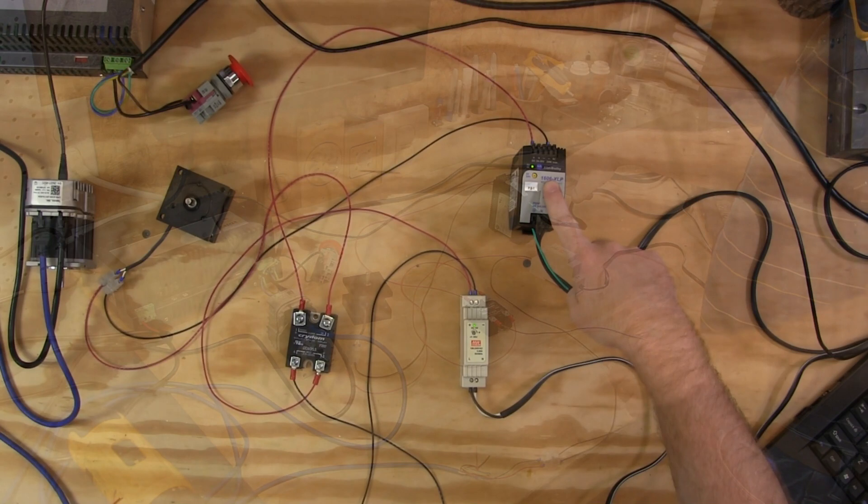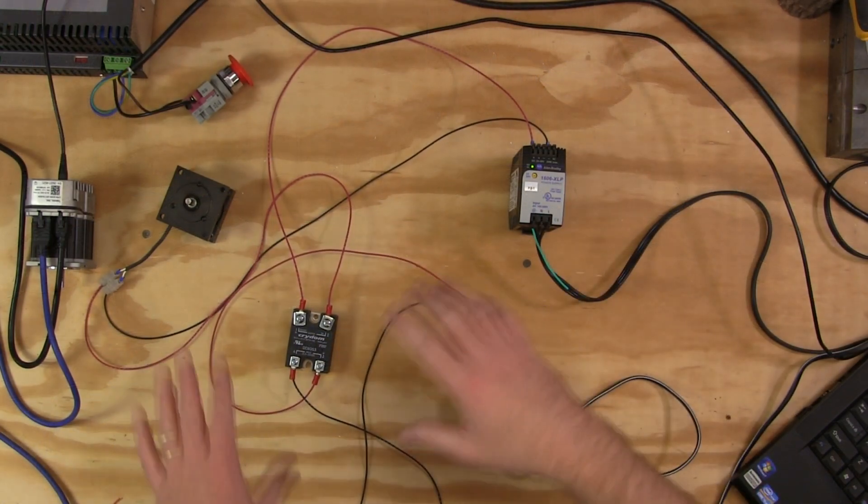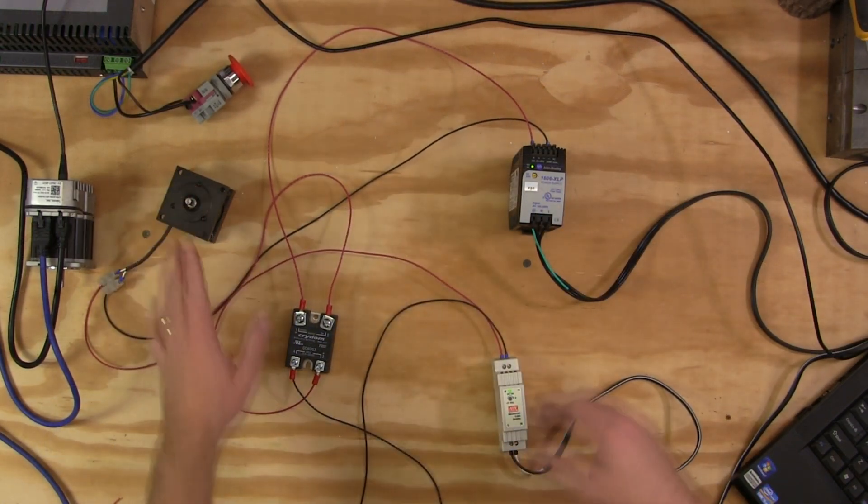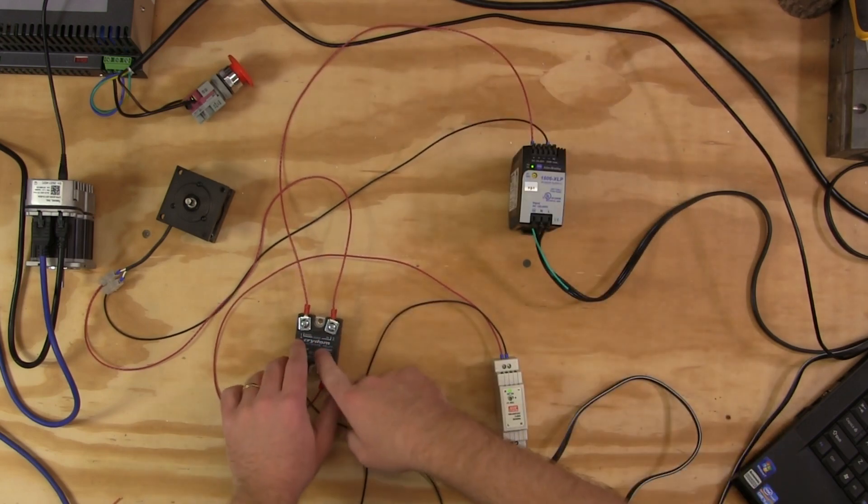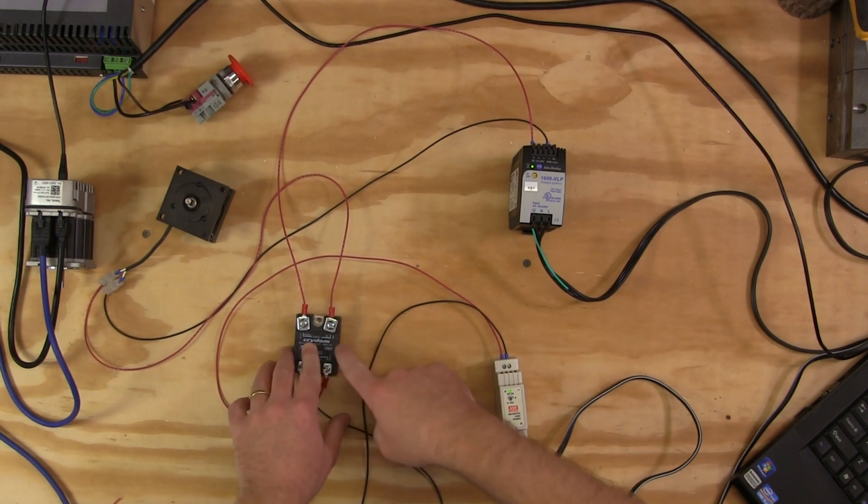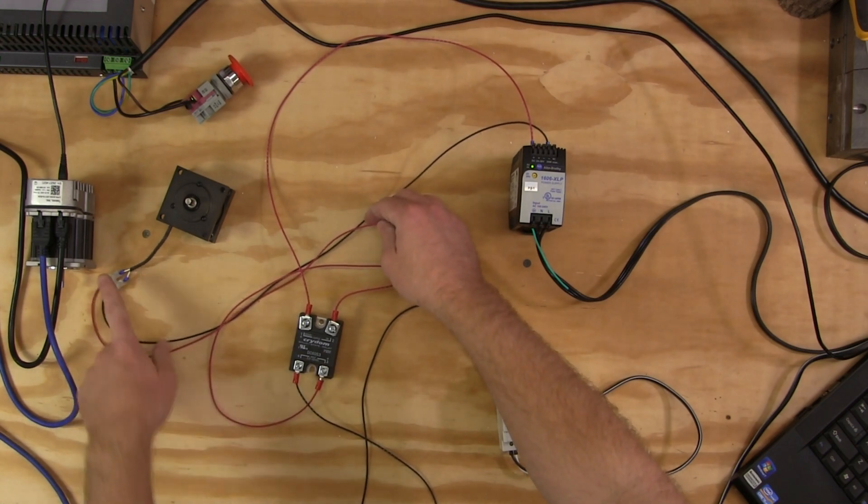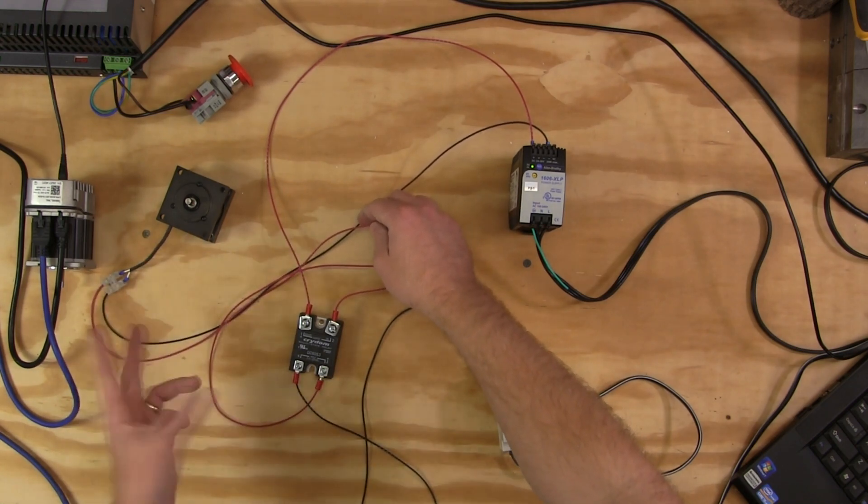Alright, so very quickly the wiring. On the 24 volt DC power supply that actually energizes the brake, the positive 24 coming out goes to the positive leg of the output side of this Crydom relay. The other end of that or position two goes to one leg of the brake. The brake is an electromagnet. It is not polarity sensitive.